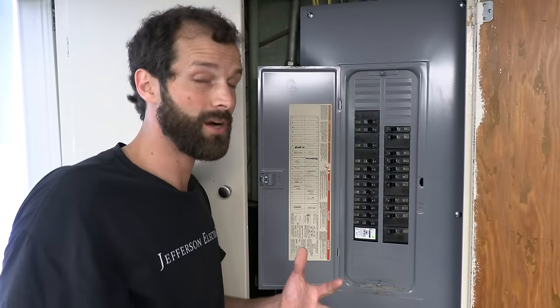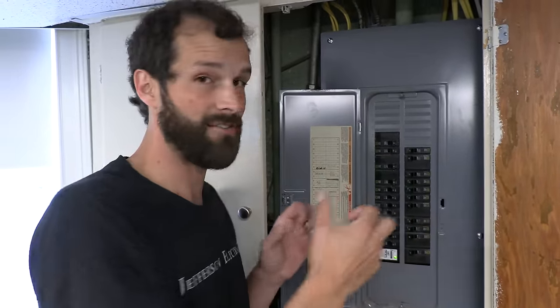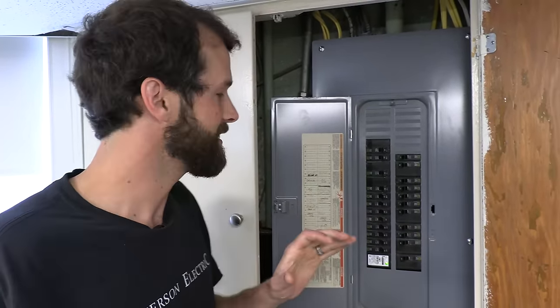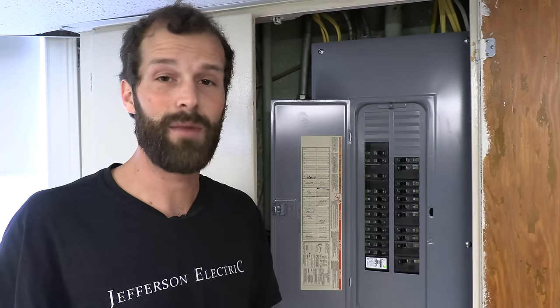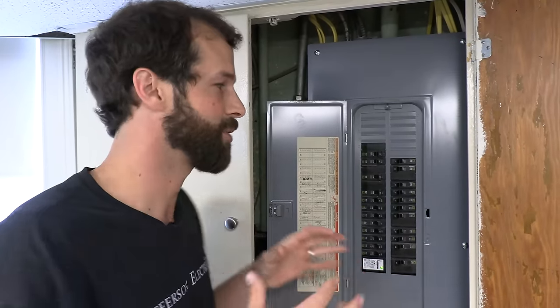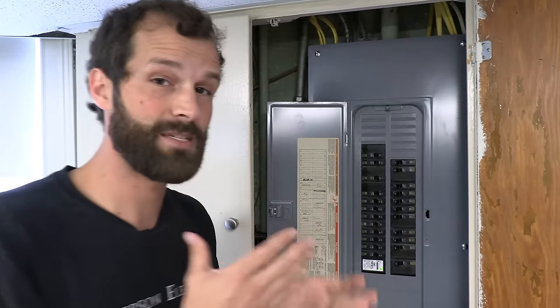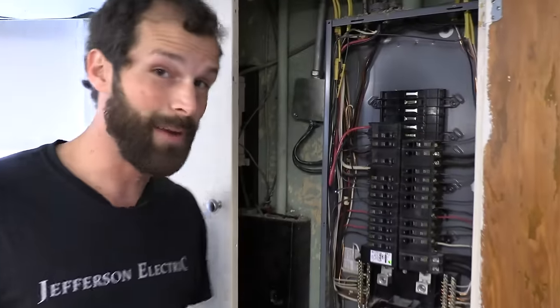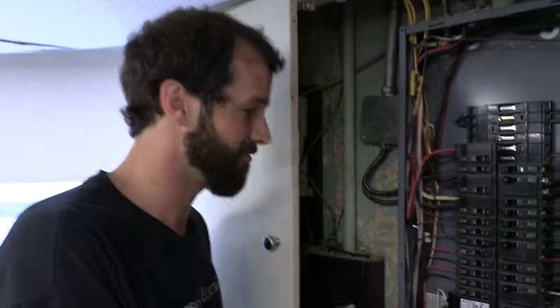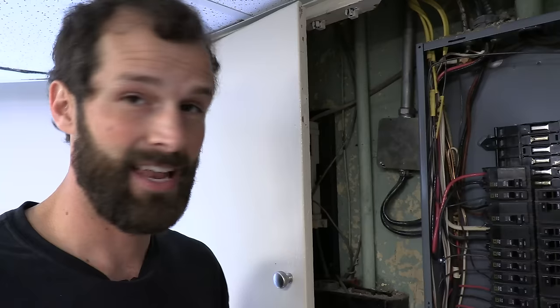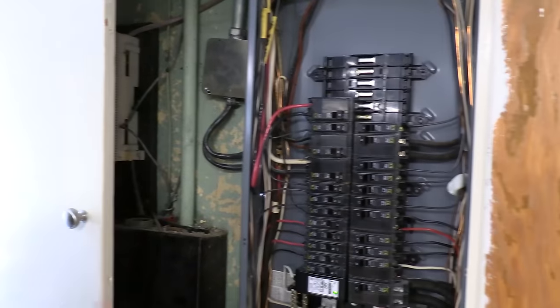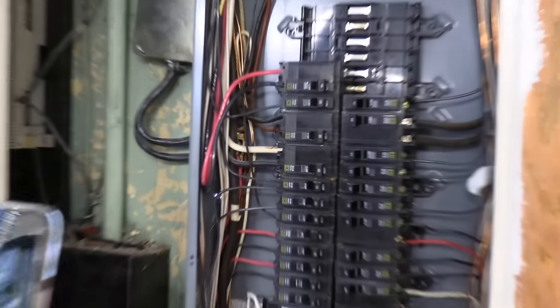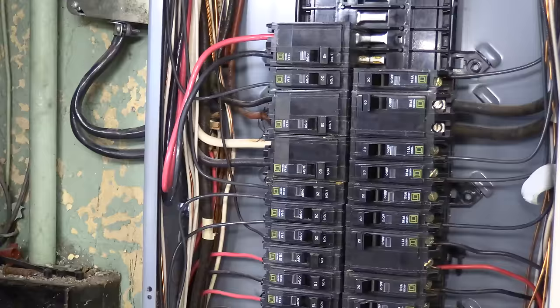Now, one thing to watch out for if you're comfortable is taking the panel cover off carefully. And some of these circuits might not be in use. They might be empty breakers. You'll never find those circuits unless you pull the cover off and check. And spare circuits must be identified as such. So a couple of things I'm going to do before getting started is one, I want to confirm that every breaker has a wire connected. And I'm not dealing with a breaker that's not in use. Trying to find it, wasting time. All these breakers have wires connected. Every breaker is in the on position. I'm going to snap a picture before I get started.